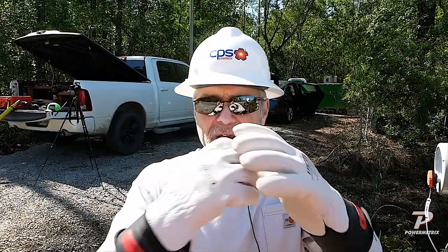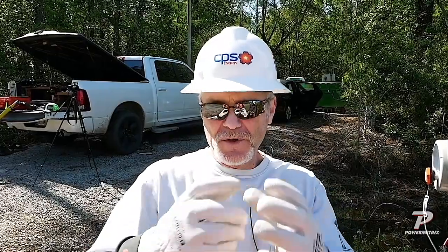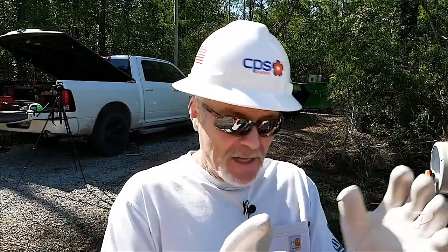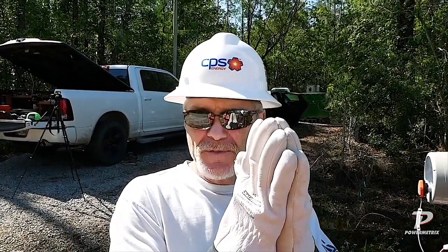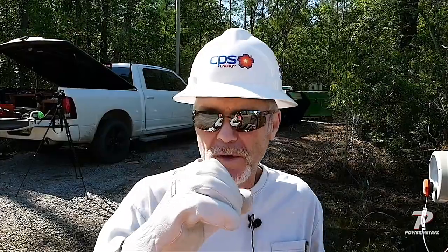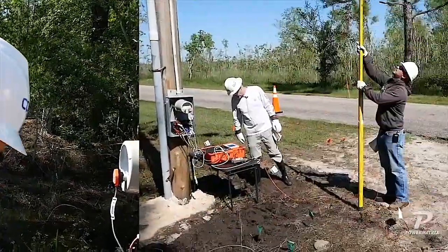It's the same as if you're using one flex and doing 3 phases—it'll give you one solid green and then two open circle greens, because you're going to have to move that flex to the others. In this case, we're going to have to move the high volt probe. So it's letting you know you're connected up, and this is what he did to match it up—it's not telling you probe's missing, it's saying you're good to go now. We know you've got the one probe connected on one of the lines, and you're just going to have to move the actual probe around. So that's what those open circles are telling you—you're going to have to move the probe.